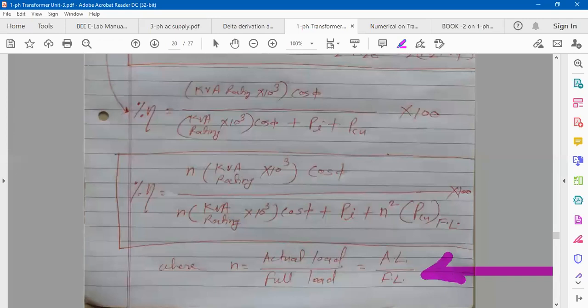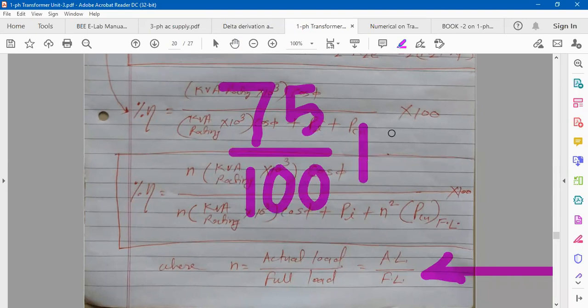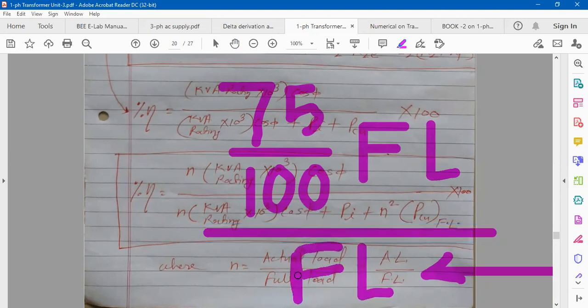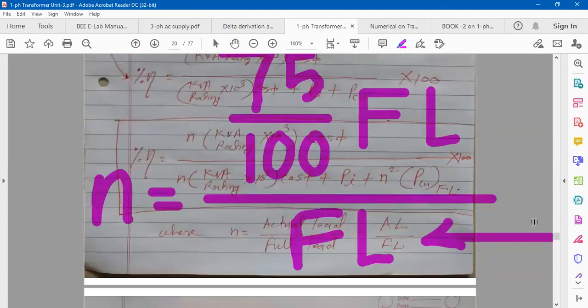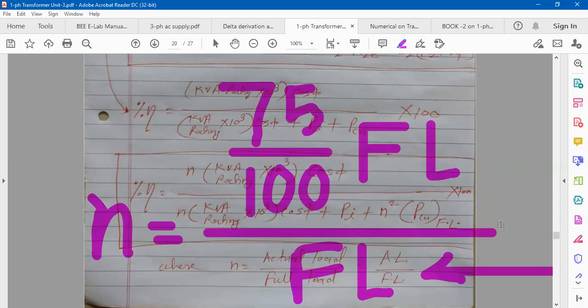Suppose you are asked to calculate efficiency when the load on the transformer is 75% of its full load. What will be the value of N? N equals actual load upon full load. So actual load is 75% of full load, upon full load — full load cancels — and N will be 0.75.